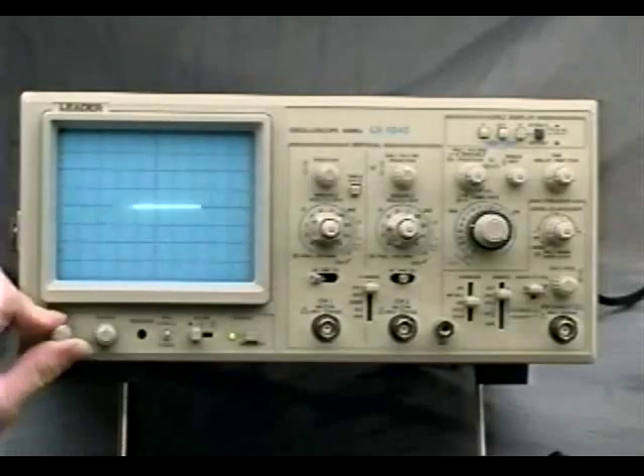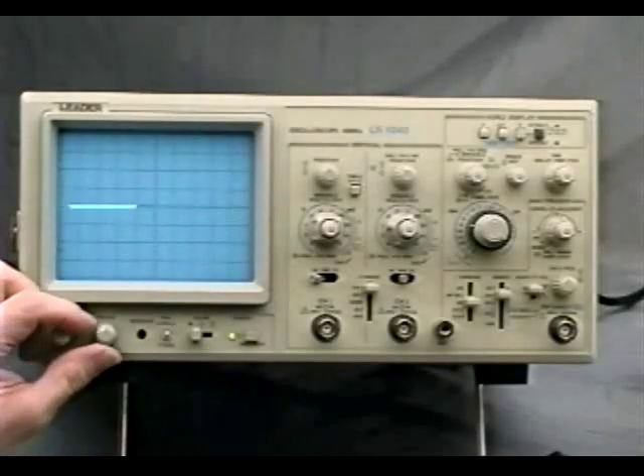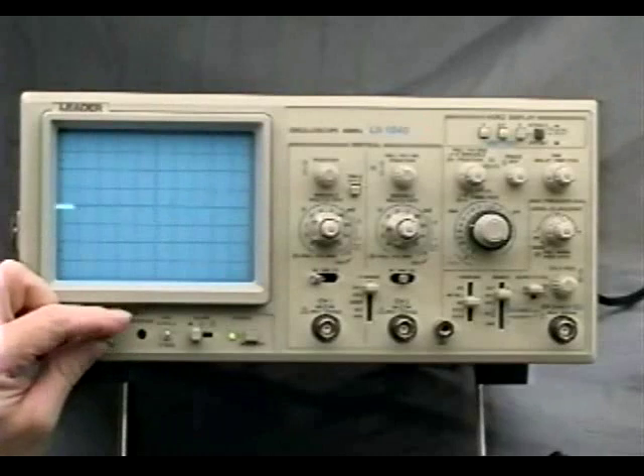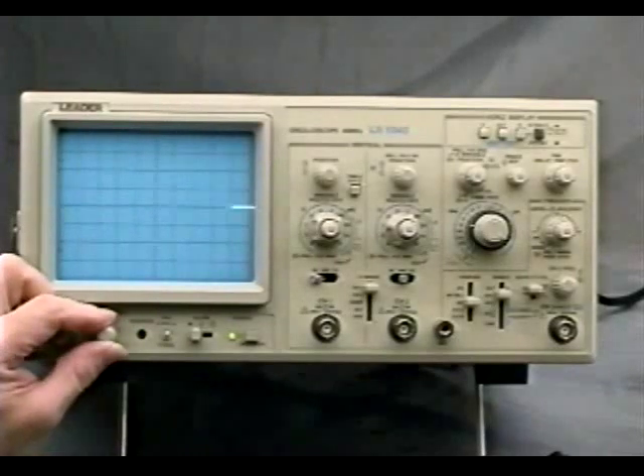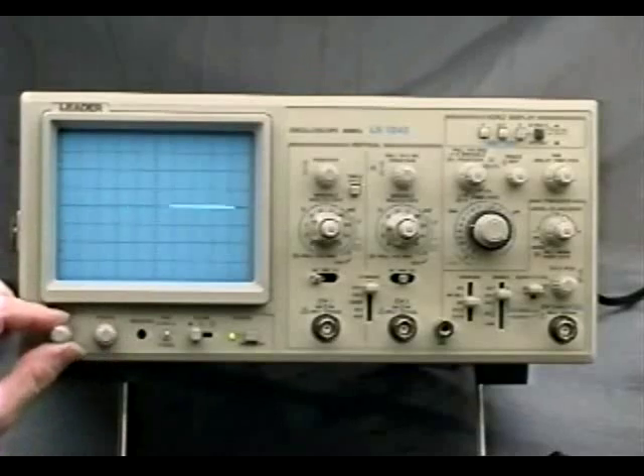Advance the intensity control to make the trace visible on the screen. For the best measurement accuracy, keep the trace intensity down to the minimum level necessary. Using the focus control, adjust for the sharpest trace possible.